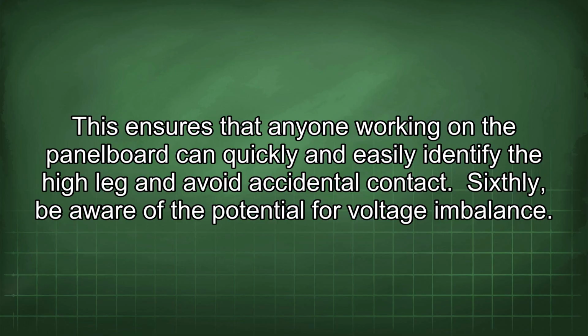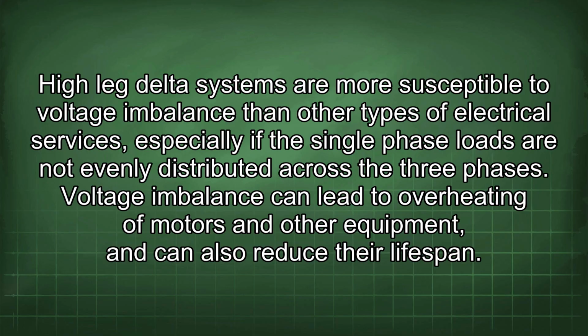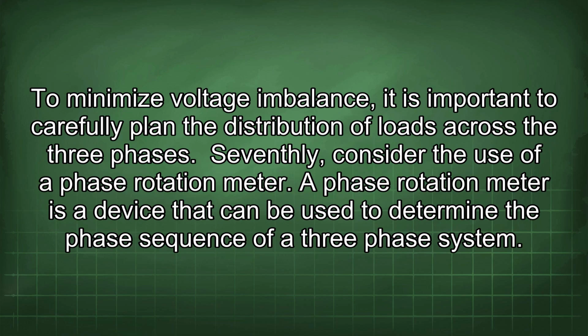Sixthly, be aware of the potential for voltage imbalance. High leg delta systems are more susceptible to voltage imbalance than other types of electrical services, especially if the single-phase loads are not evenly distributed across the three phases. Voltage imbalance can lead to overheating of motors and other equipment, and can also reduce their lifespan. To minimize voltage imbalance, it is important to carefully plan the distribution of loads across the three phases.